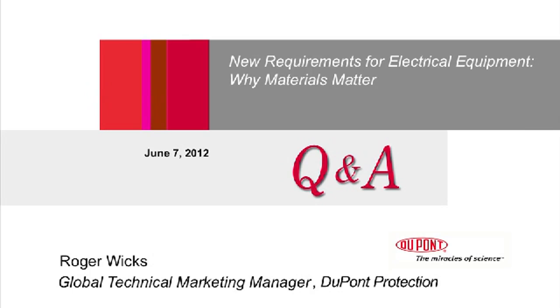Because of the mica content, they're around 50% mica content. They're not as strong mechanically as the type 410 papers. Thank you, Roger. Question came up. The relative stiffness of Nomex type 410 is higher than conventional kraft paper. What thickness of Nomex would be required to achieve the same stiffness inherent in 10 mil kraft? And then another question to that is, how does the stiffness of the laminate compare to the material that was mentioned before?